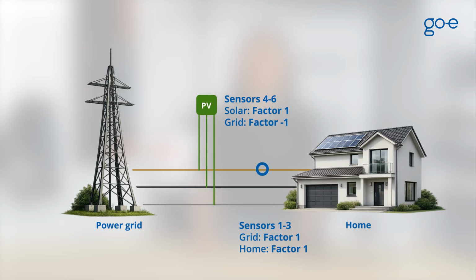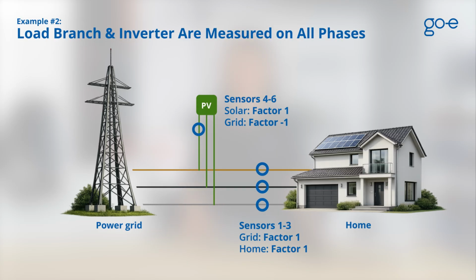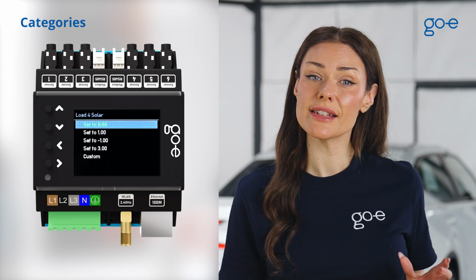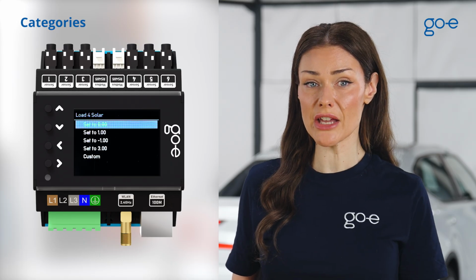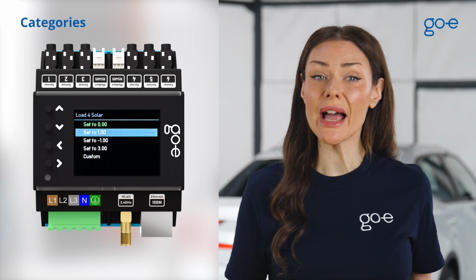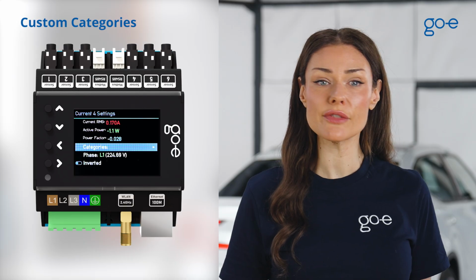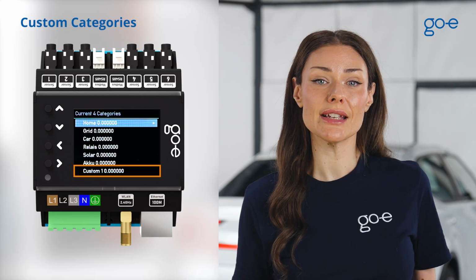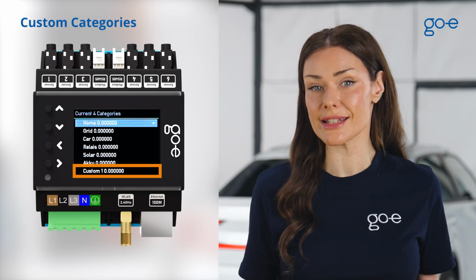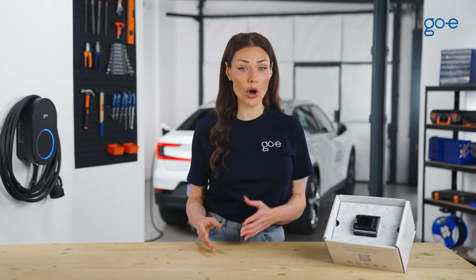Let's assume you're measuring both the load branch and the inverter on all phases. In this case, your categories will look slightly different. You'll need to subtract the solar production from the grid measurement, so you'll set the factor to -1 for the solar measurement. If you're measuring just a specific device, for example, a boiler, you can assign it to a custom category, such as Custom 1. You can rename this category later if you like. There's no need to assign this to grid or home since you're already directly measuring these currents.